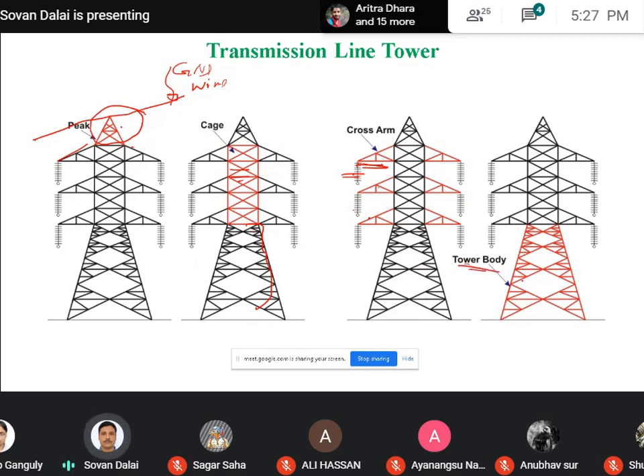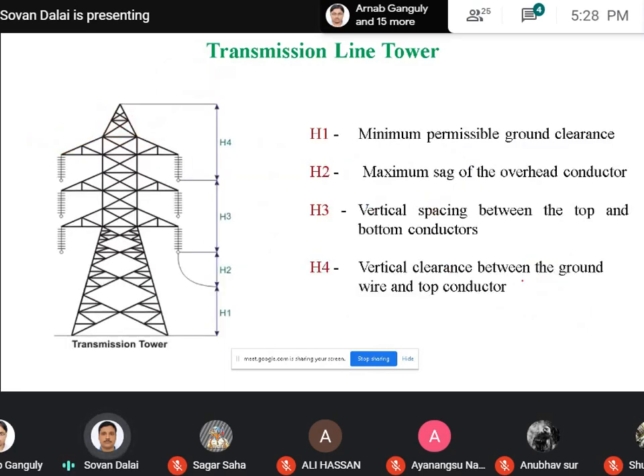So these are the major portions of a lattice type of structure, and the height of the transmission line is defined as consisting of four different sections: H1, H2, H3, and H4. What is H1? H1 is the minimum possible ground clearance. If the bottom conductor sags, it does not touch the ground. So there is a distinct clearance between the ground and the bottom portion of the conductor.